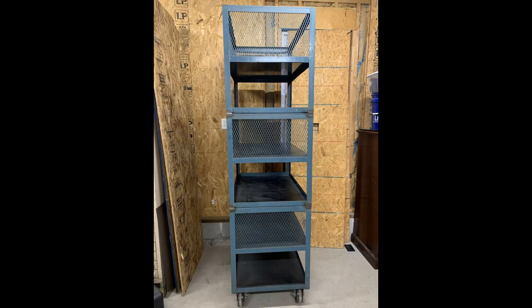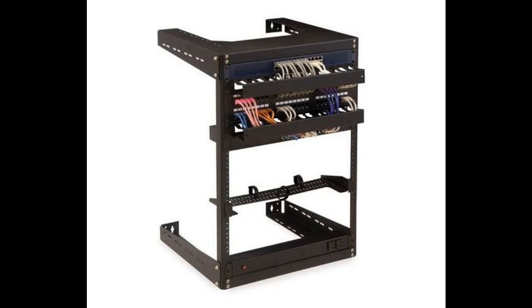Avoid mounting your device to ungrounded metal. If you rack mount your device, make sure the rack is grounded. Otherwise, you're mounting your device to an antenna, for all intents and purposes, for lightning. The more surface area, the more likely that metal and your stuff can get struck by lightning.